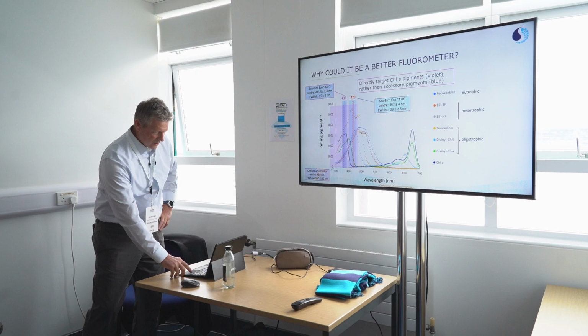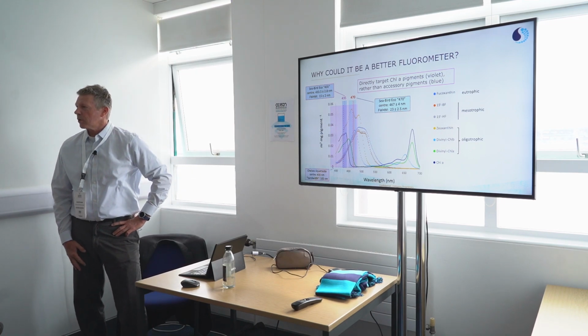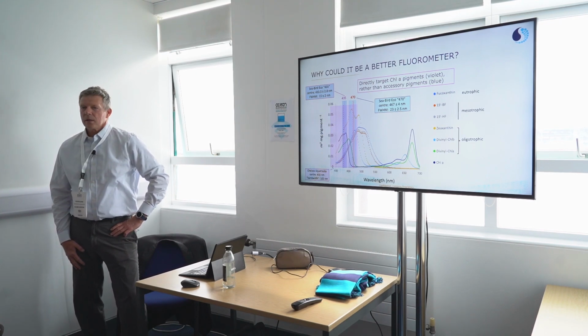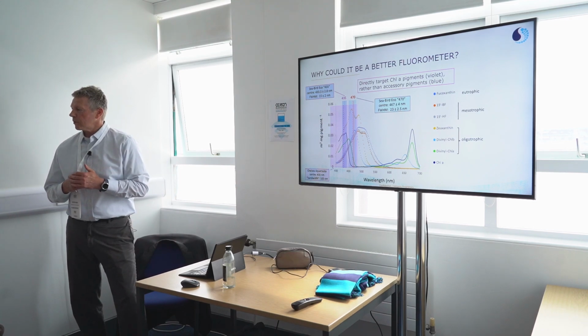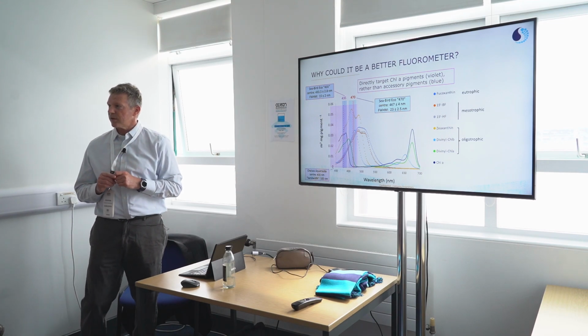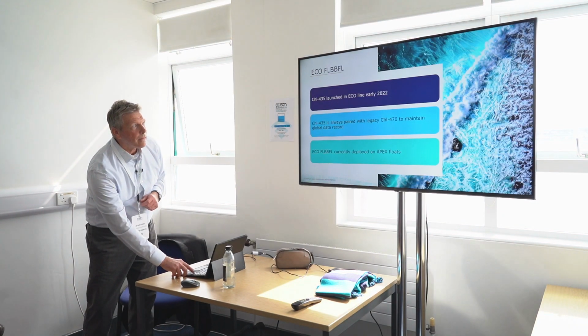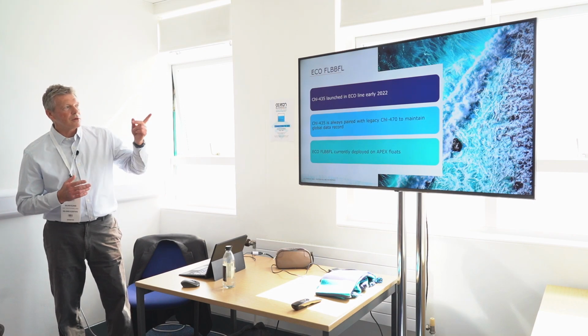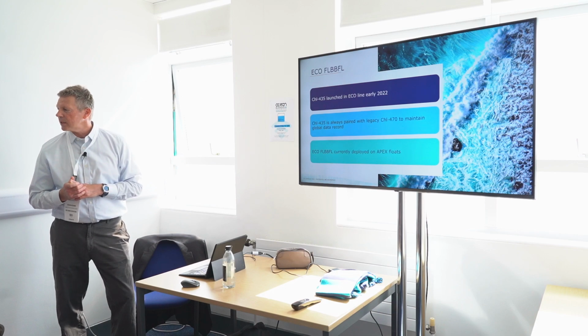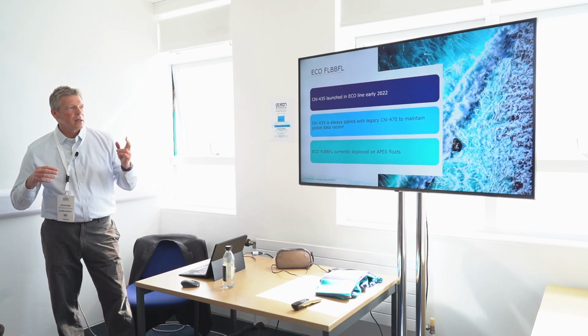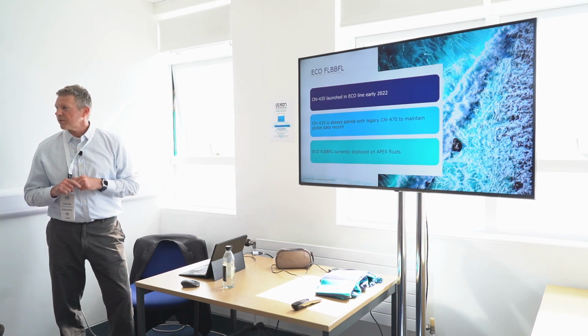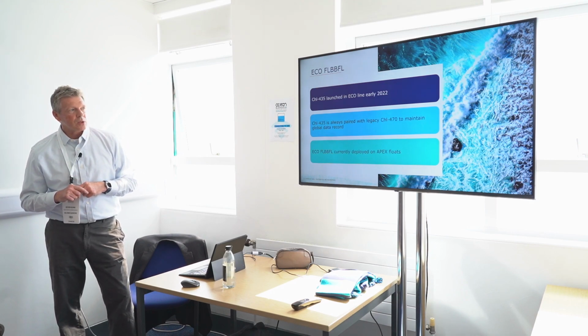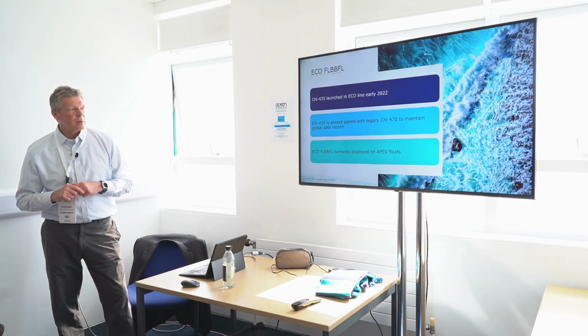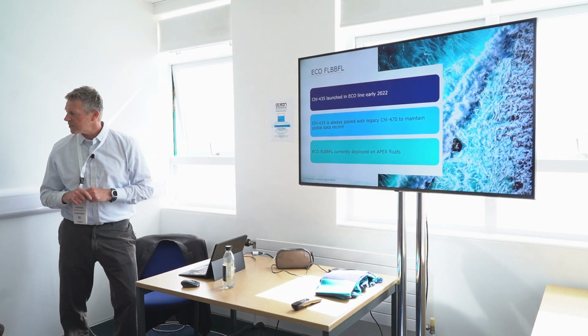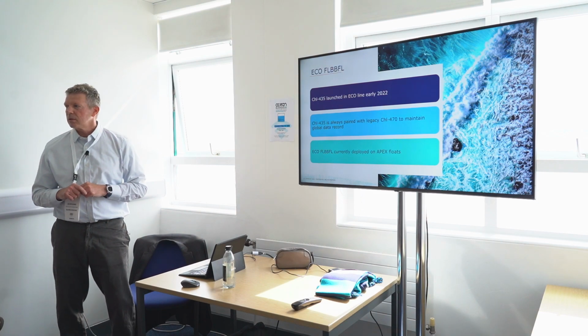Yeah. Thank you. So that was really coming at the request of some of our BGC Argo users, because they think there's maybe a chance to decrease the geographic variability of chlorophyll measurements overall by having this dual measurement of the existing 470 and the new 435. The capability of adding a 435 to the ECO triplets was added in early, I think, 2022. And the way we sell it right now, it's always paired with the 470, so you have a reference measurement that gives you consistency of the global data records, at least for comparison. I think most of the ECOs, we call them internally FL, BB, FL, so fluorescence, backscatter, fluorescence, are currently deployed, I think, on Apex floats, and there's some on French PROVOR floats and Kei floats.